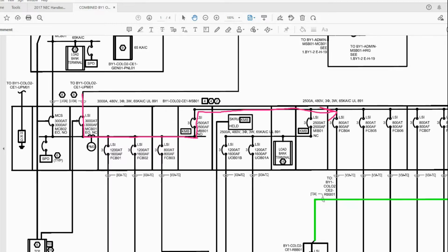Now that's when we're in maintenance bypass. Normally the way this works is we send power out through FCB 1 and 2 for our paralleling system, and it comes back from the UPS on our UOBs. This 480 volt system, when it converts from AC to DC, is not going to be in the same frequency as our utility with the output of our UPS system. So sometimes we have to put these UPSs into what is known as maintenance bypass. So I'm about to show you that right here.